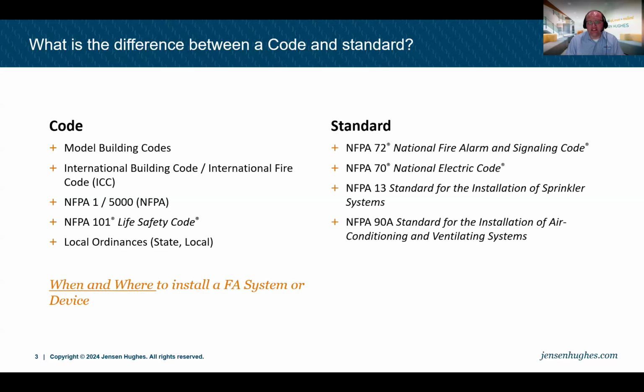So those installation standards are things that we're very used to hearing about. NFPA 72, that's the National Fire Alarm and Signaling Code. NFPA 70, that's the National Electric Code. NFPA 13, the Sprinkler Code. 90A for air conditioning and ventilating systems, etc. And these are really installation codes that tell us how to install, let's say, a fire alarm or life safety system itself, or a device that's part of that system. So that's really the big difference between a code and a standard.